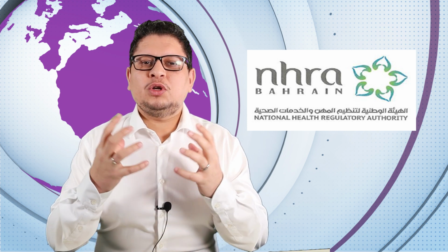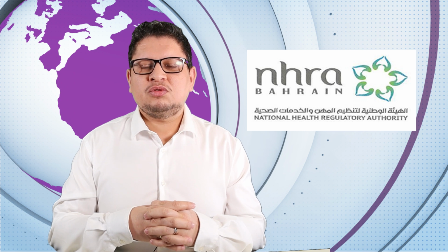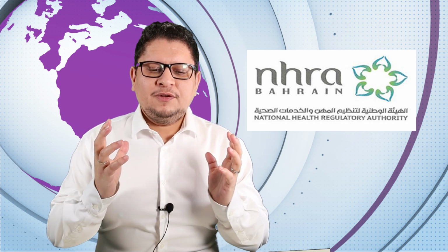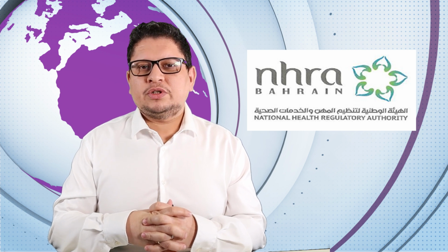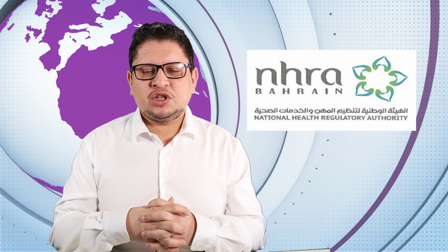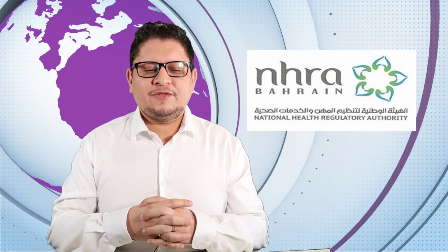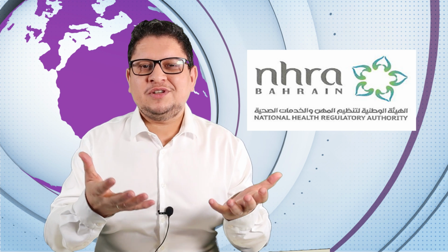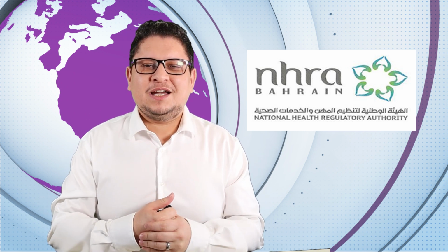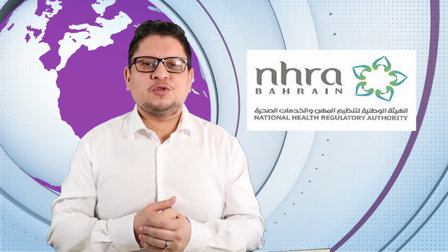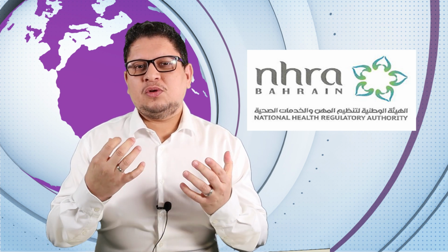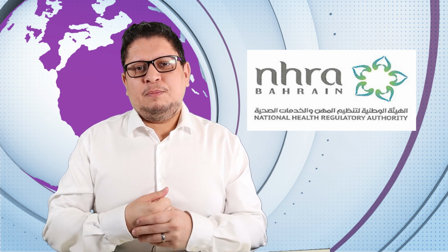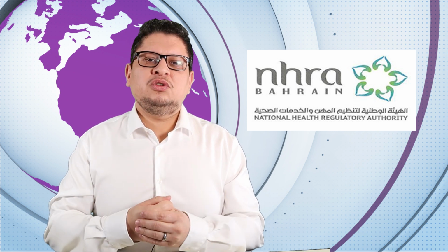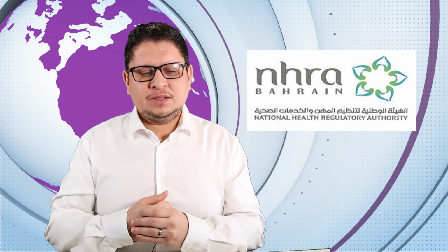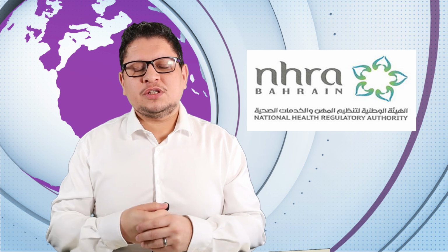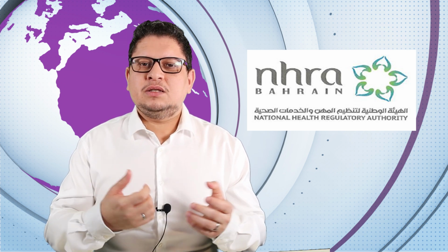So if you are planning to have it only once, then it doesn't need to be registered because it's an exceptional situation. If you have medical devices that are imported in Bahrain for research and educational purposes, there is no need also to register. If you have some personal imported medical devices, so if you are traveling and you have with you your personal medical device because you are a user of it, then it's also not considered to be registered. If you also have a custom-made device or a specific patient device that has to be delivered, it also doesn't need to be registered. And the last one is the samples for exhibition or for conferences. So if you are traveling there for a conference, then it's not needed also.